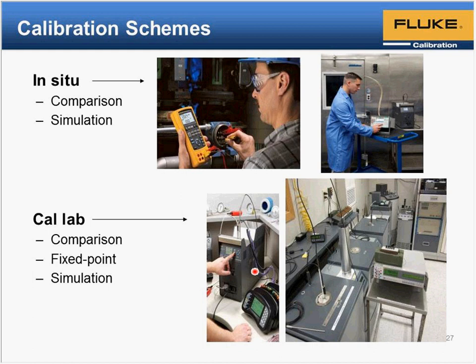But most thermocouple calibrations are done just like any other temperature probes. You have a bath that provides a temperature, with thermocouples in the furnace or the bath along with a reference probe, and you connect the thermocouple to a readout like shown here in the left-hand picture.